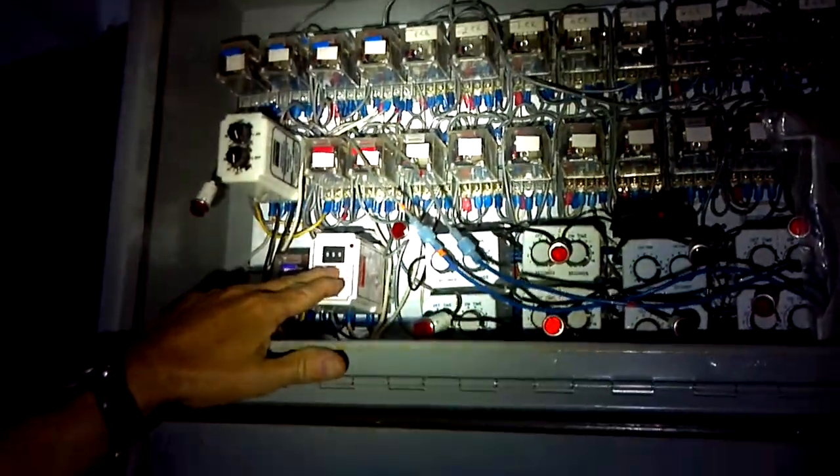So you got eight air valves — I saw pictures of this and thought it was down in there. I was wondering what all these hoses were. This mechanism is for the controller that comes in through here. You got little air solenoids in there to control these, and the relaying that operates — you can set your cleaning schedule by how many minutes between cleaning.